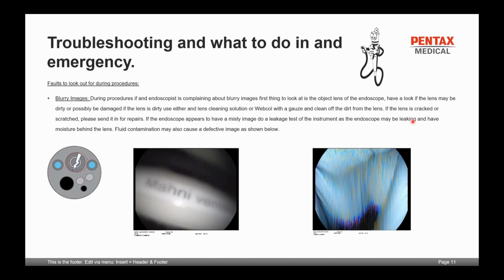If the endoscope appears to have a misty image, do a leak test, as the instrument of the endoscope may have a leak on it, and there might be moisture trapped behind the lens. Fluid contamination may also be a result of a defective image, which is this image over here. So that's an indication of a fluid contaminated or fluid behind your objective lens. And that's an indication of an electrical fault caused from fluid. And then obviously a cracked or scuffed objective lens.